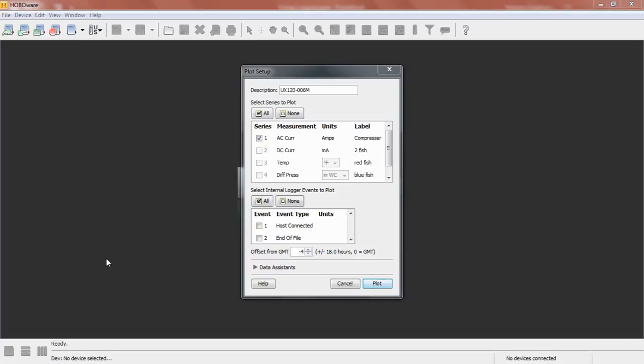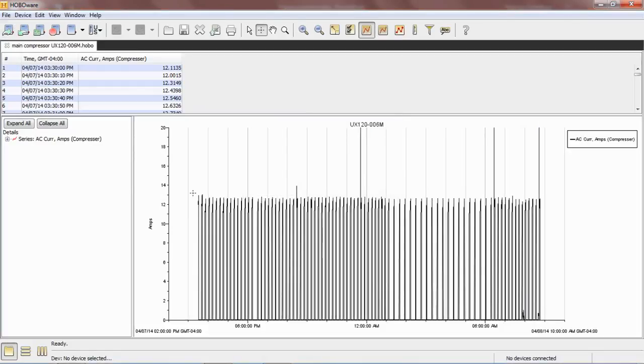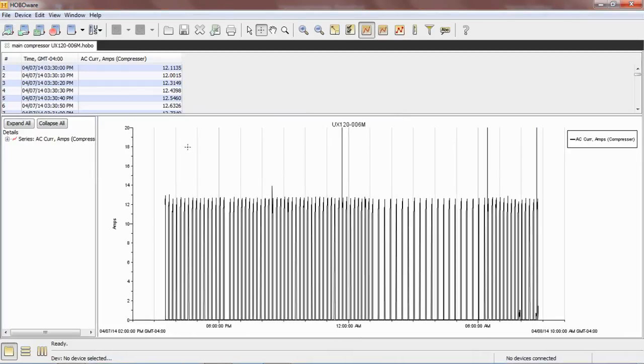the total. But again, because it's what's called a constant load, variable time, or fixed load if you will, it would be a good candidate for runtime monitoring. So I already went to file and open data file, so let's plot the data. So there's our data, and we can see from this we're logging at a 10-second logging interval.